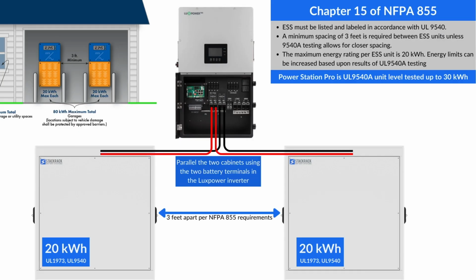Now, a really common use for the SRB4 cabinets is using these cabinets in conjunction when you have to stay under 20 kilowatt hours per cabinet and you need to keep these cabinets 3 feet apart. The ability to tie into the Luxpower inverter using both battery terminals makes paralleling these cabinets very simple. So in this situation, you could put up to four batteries on one cabinet, four batteries on the other cabinet. You can run communication through the conduit lines between both cabinets using shielded Cat5 cable. And then using the battery cables being the same length, you can parallel within the inverter and you can meet these requirements and offer up to 40 kilowatt hours of battery storage with less than 11 inches coming off the wall.